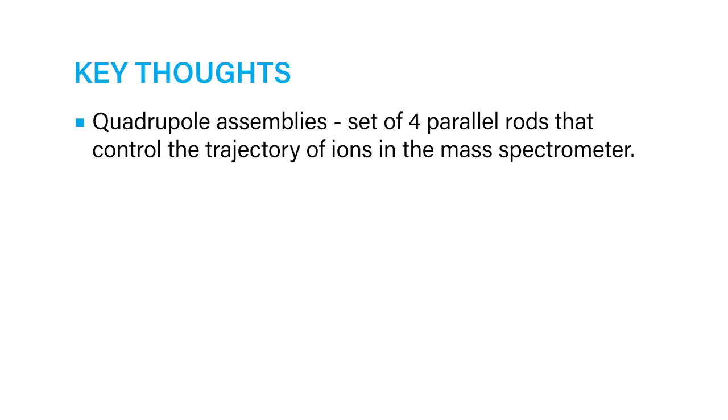I hope you found this information on quadrupole theory and use to be helpful and informative. To review, quadrupole assemblies are a set of four parallel rods that work together to control the trajectory of ions in the mass spectrometer.